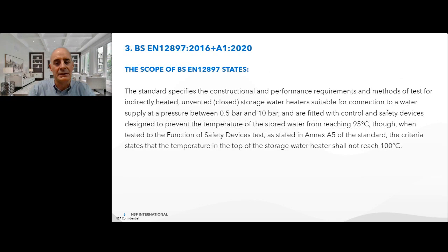The scope of BS 12897 states that the standard specifies the constructional and performance requirements and methods of test for indirectly heated, unvented closed storage water heaters suitable for connection to a water supply at a pressure between 0.5 bar and 10 bar, and are fitted with control and safety devices designed to prevent the temperature of the stored water from reaching 95 degrees. Though, when tested to the function of safety test, as stated in Annex A5 of the standard, the criteria states that the temperature in the top of the storage water heater shall not reach 100 degrees C.